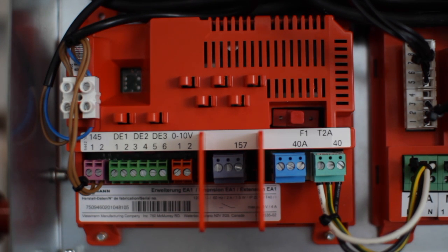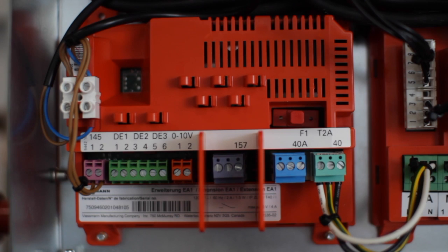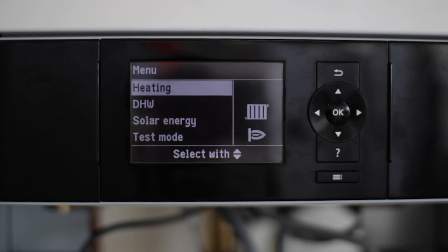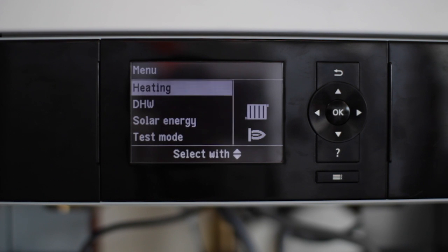There are three inputs. Either can be used for the external demand, but please remember only one external demand can be wired to the boiler. Once you have connected your dry contact to the DE input you selected, the following program changes will need to be made in coding level 2.